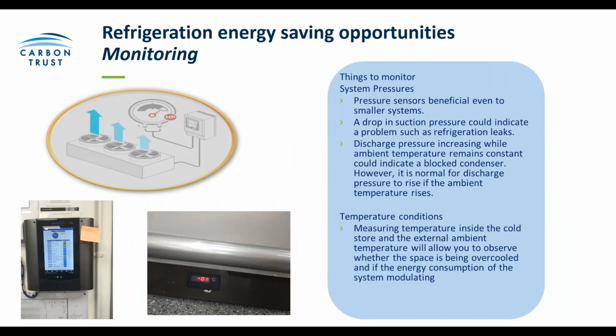In terms of monitoring, it's good to keep tabs on both the pressure and temperature going on in a system. The temperatures will give you a really good indication as to whether a system is working as it should be. It can give you an indication about whether there are any refrigeration leaks that need to be looked into as soon as possible.